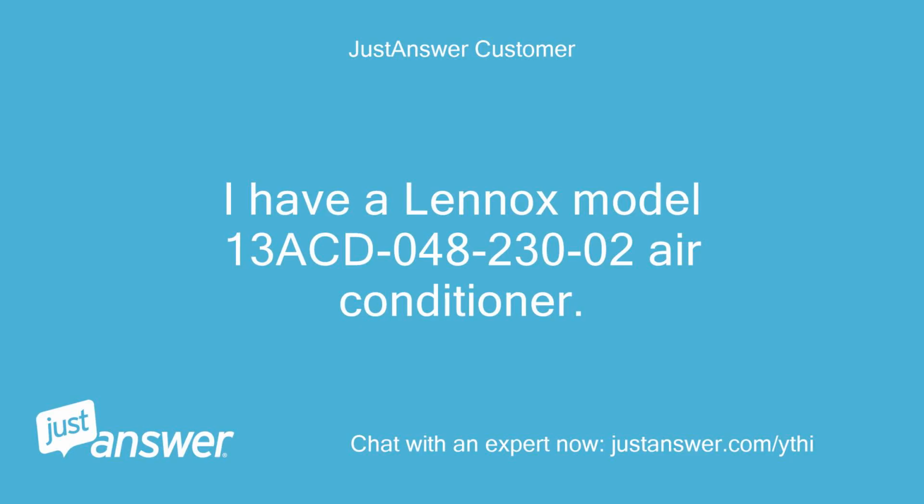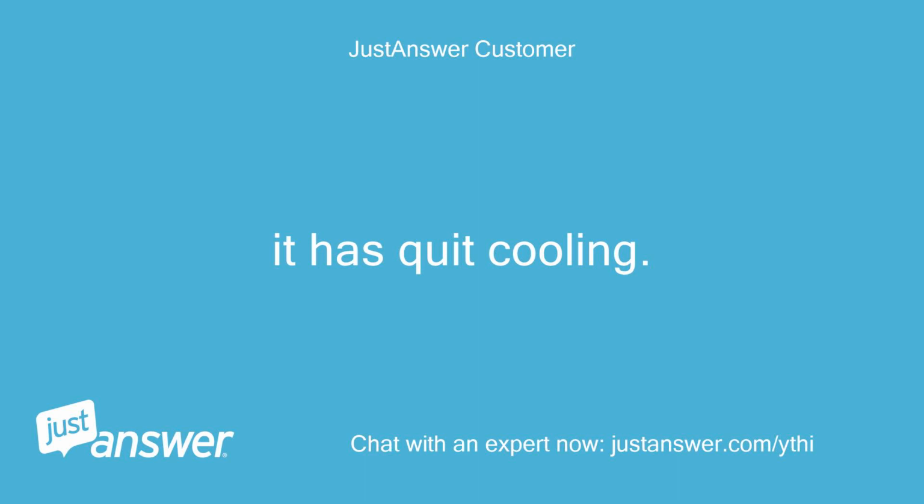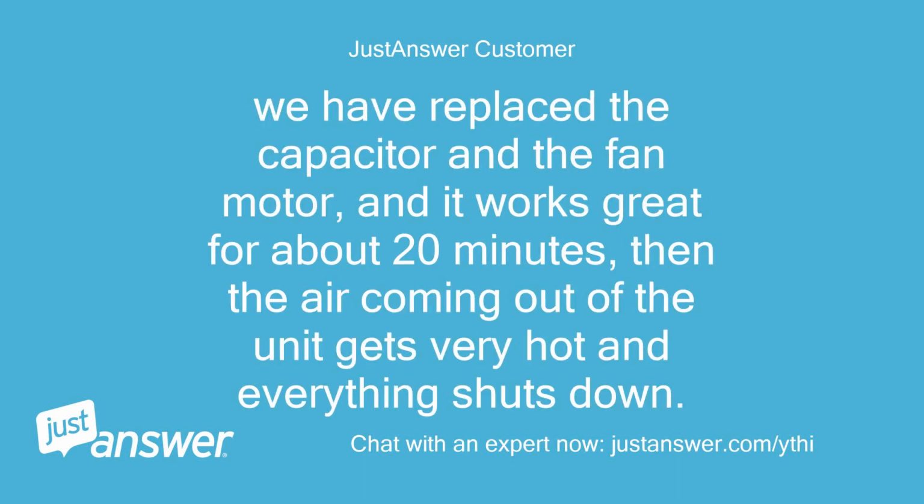I have a Lennox model 13ACD-048-230-02 air conditioner. It has quit cooling. We have replaced the capacitor and the fan motor, and it works great for about 20 minutes, then the air coming out of the unit gets very hot and everything shuts down.